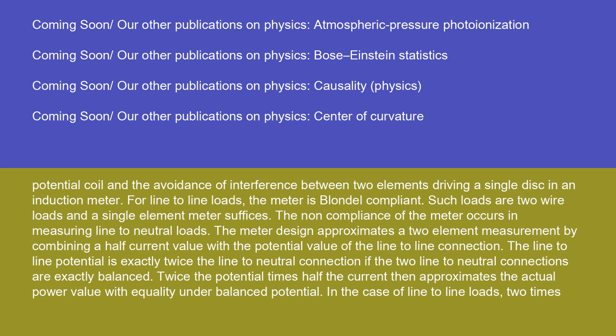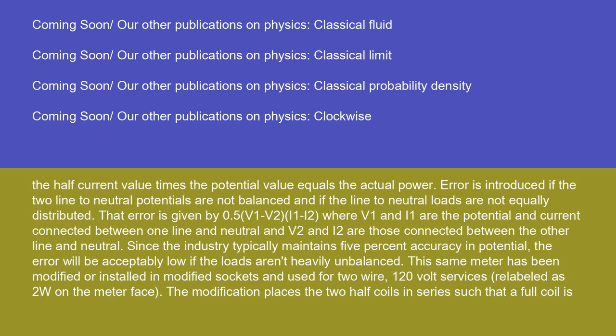For line-to-line loads, the meter is Blondel compliant, as such loads are two-wire loads and a single-element meter suffices. The non-compliance of the meter occurs in measuring line-to-neutral loads. The meter design approximates a two-element measurement by combining a half-current value with the potential value of the line-to-line connection. The line-to-line potential is exactly twice the line-to-neutral connection if the two line-to-neutral connections are exactly balanced. Twice the potential times half the current then approximates the actual power value under balanced potential. Error is introduced if the two line-to-neutral potentials are not balanced and if the line-to-neutral loads are not equally distributed.